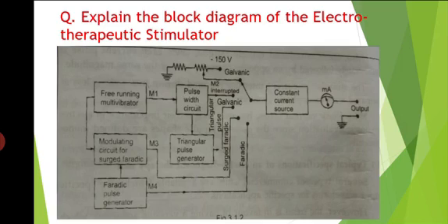The output pulse from the monostable provides an interrupted galvanic output whose rate as well as duration can be independently controlled. Another astable multivibrator produces short duration pulses called Faradic current. Faradic current is usually modulated at a frequency set by the multivibrator M1 in a mixer circuit, M4. Since the modulation of Faradic pulses takes place with a low rate of increase and decrease, the output of M4 is a surged Faradic current.